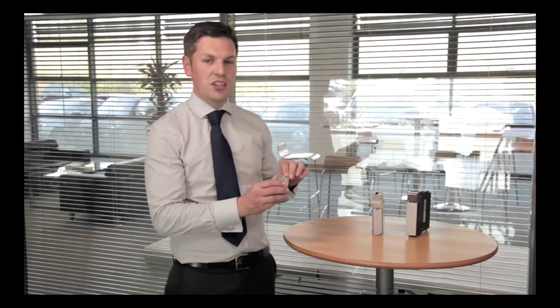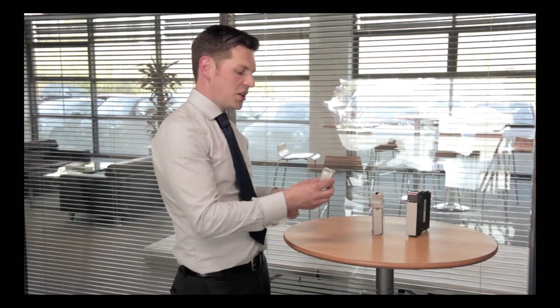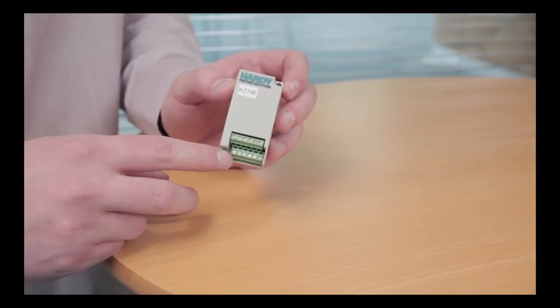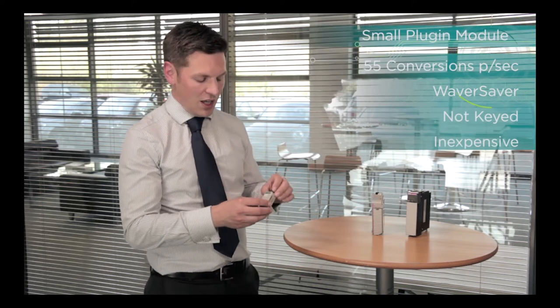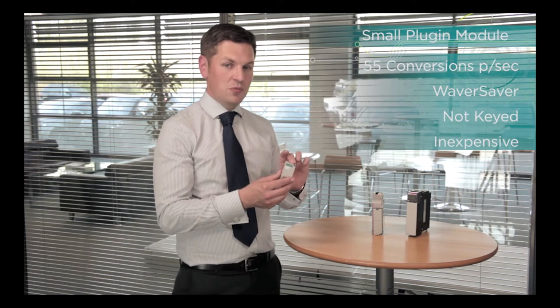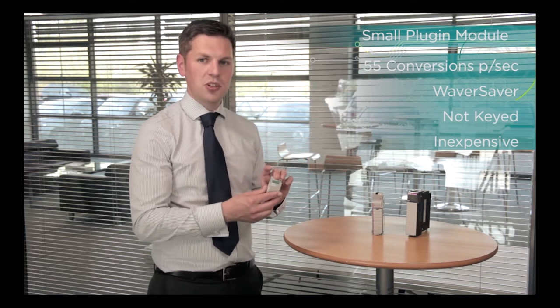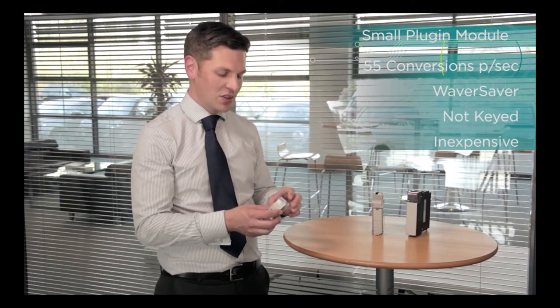It's basically an inexpensive way of getting weighing data into your PLC. Plug it in, feed the weight scale module into it, and then it will give you real tag values for weight. Despite being inexpensive, it still does 55 conversions a second and it's a really useful intro to the Hardy range.